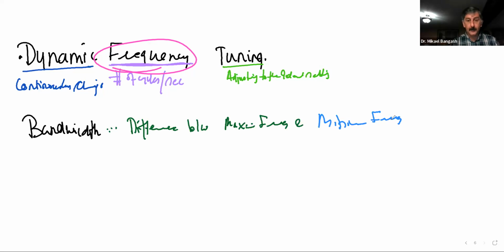That will happen when a transducer produces sound waves of more than one frequency rate. And as a matter of fact, for our imaging transducers or pulsed wave transducers, we mainly said that one had a broad bandwidth, or if you don't like the word broad, you can use the word wide bandwidth. It means that when it's a broad or wide bandwidth, there will be a great difference between the maximum frequency and the minimum frequency. Did that make sense?